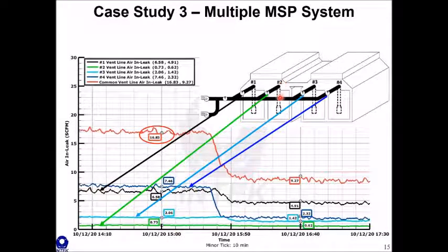Based on the design of this condenser, the primary source for air in-leakage in these 2 bundles would have to come from expansion joints or turbine seals, or from penetrations directly above the bundles on the water box side of the condensers, of which there were very few. So based on this data, we were able to conclude that there likely was very little leakage from turbine steam seals and expansion joints. This meant that the effort searching for leaks could be focused on penetrations in lines entering near the number 1 and number 4 bundles. Narrowing down the leak search area would have been impossible, leading to an arduous search process, without having a probe installed in each of the vent lines.